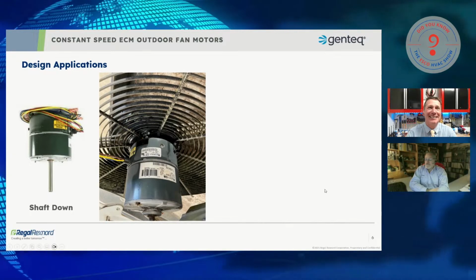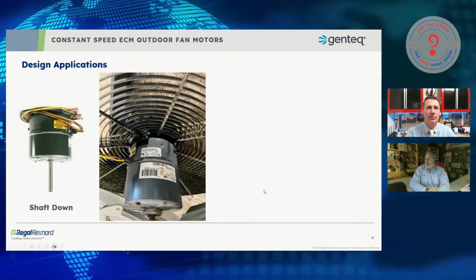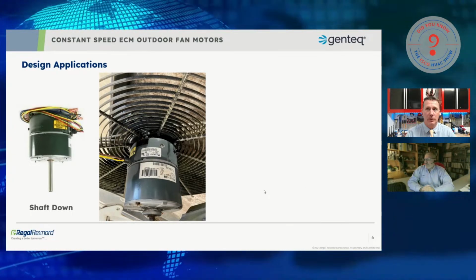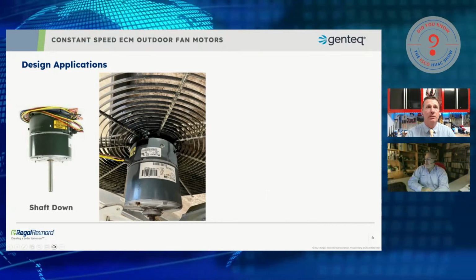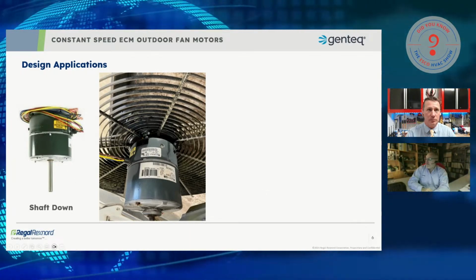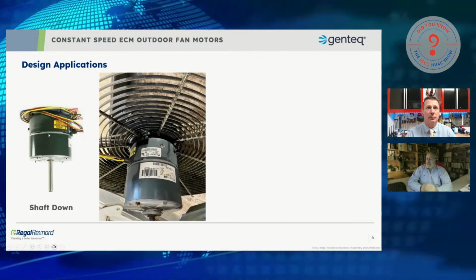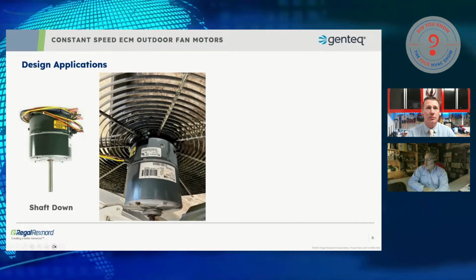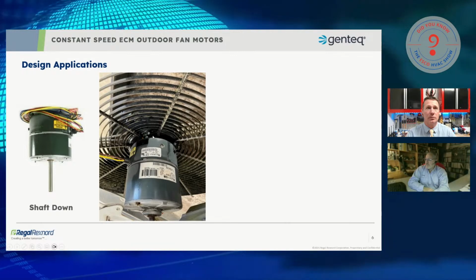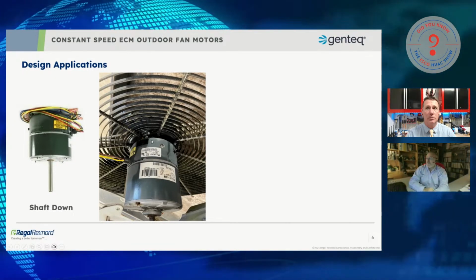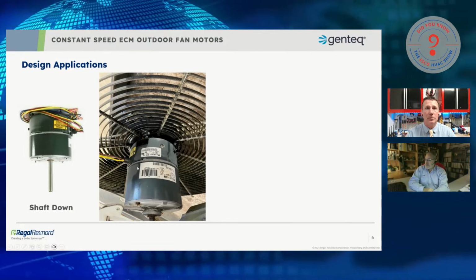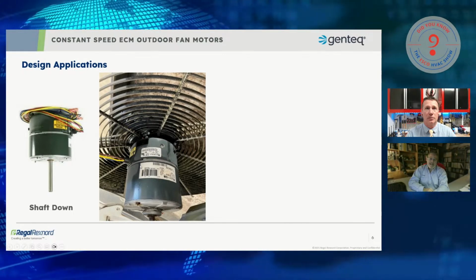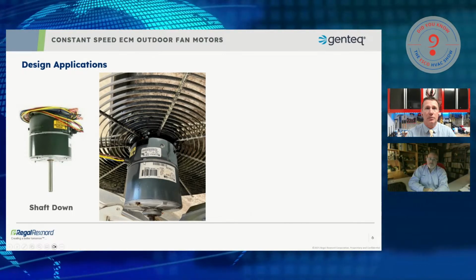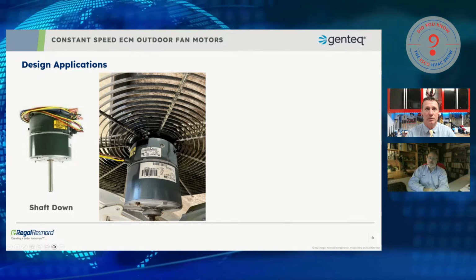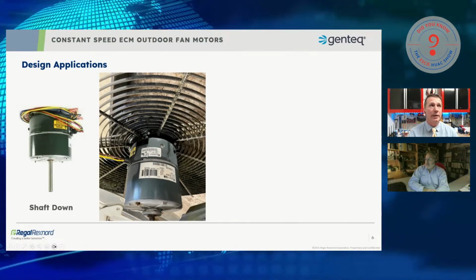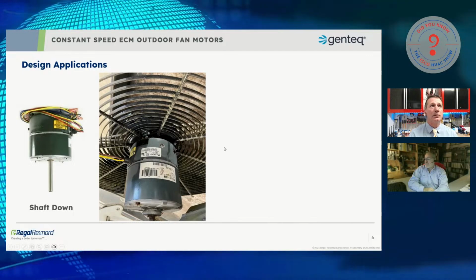So when they're built for shaft down, they look a lot like the ECM motors we see in indoor blower motor applications, where the motor control is bolted onto the back of the motor. It is bolted onto the back of the motor in the same fashion, where the molded portion is facing up. And we see that here, so that when the rain hits that, it runs off that molded portion. It's going to run down past this seam. These seams are typically not sealed. The water's allowed to run by it. Very unlikely it's going to wick back up into that electronic area. And that's going to be the typical design of a shaft down application.